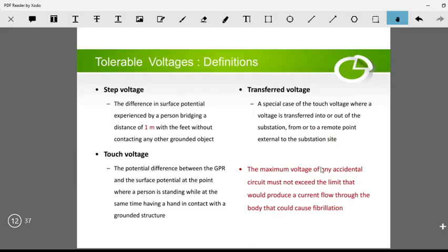So the maximum voltage of any accidental circuit must not exceed the limit that would produce a current flow through the body that could cause fibrillation. You have to make sure the voltage does not exceed this: V equals I times R, so this is IB, the body current. From that you can calculate the voltage, where R is the body resistance.